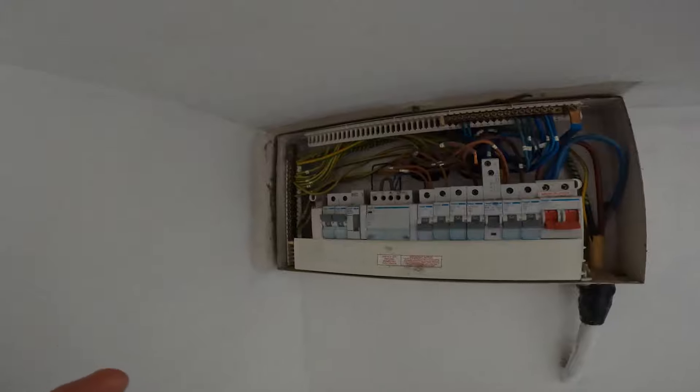When you're doing it, you just connect live to earth, go to your end, make sure you've got an earth path all the way around. Make sure everything's earthed - if you don't get a reading, it's not earthed, or you haven't plugged in your testers properly. After that, insulation resistance - bang - and if it all passes, bang it back in. Easy as that.